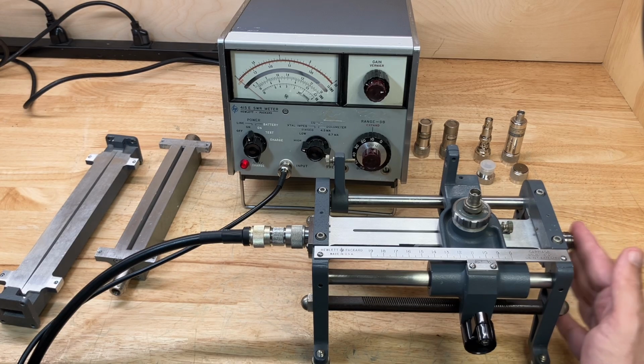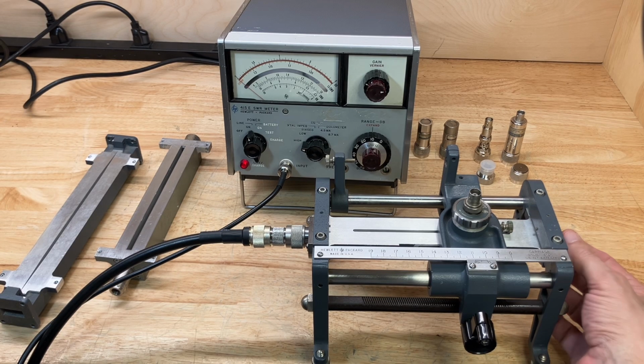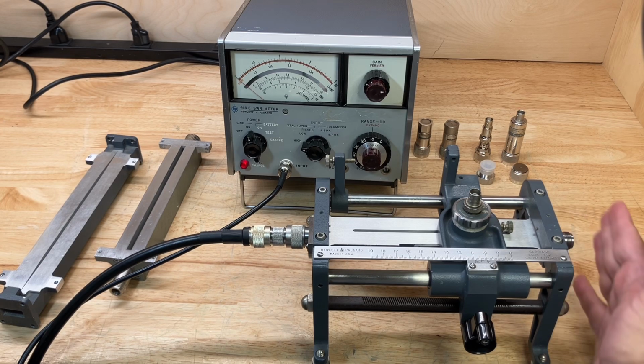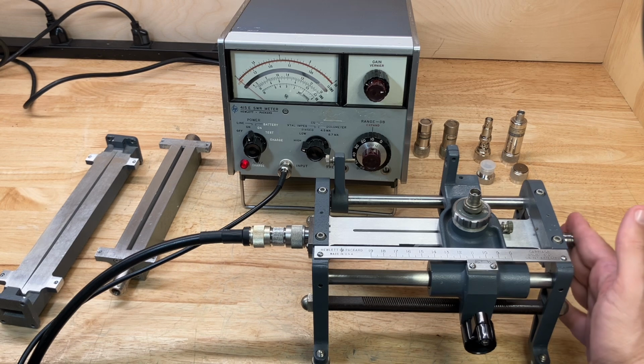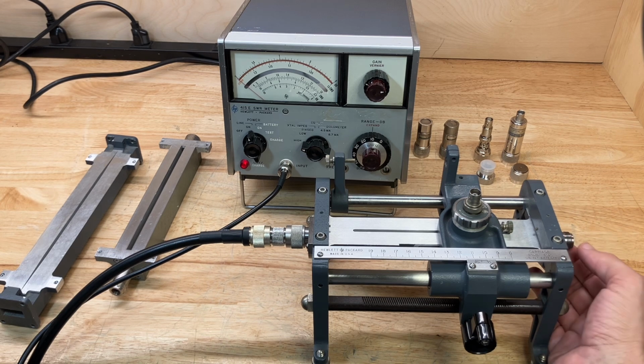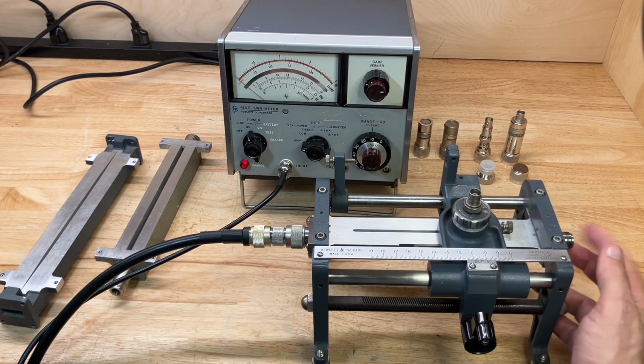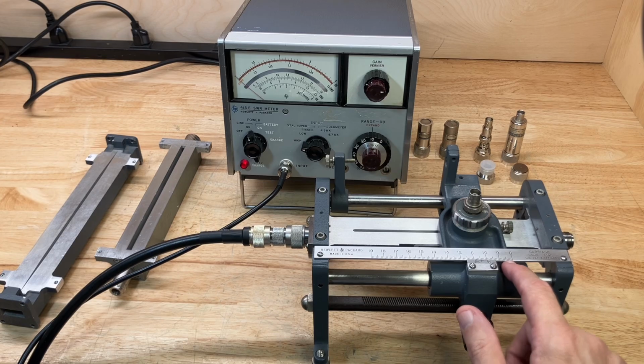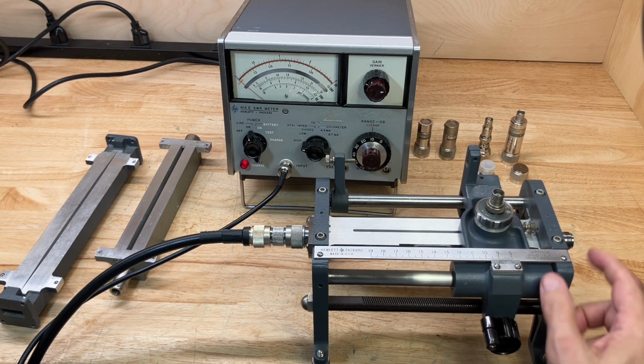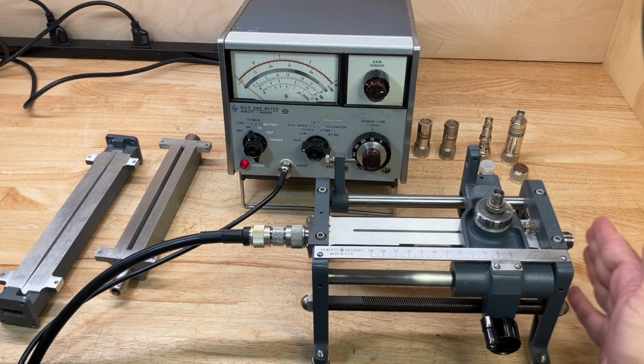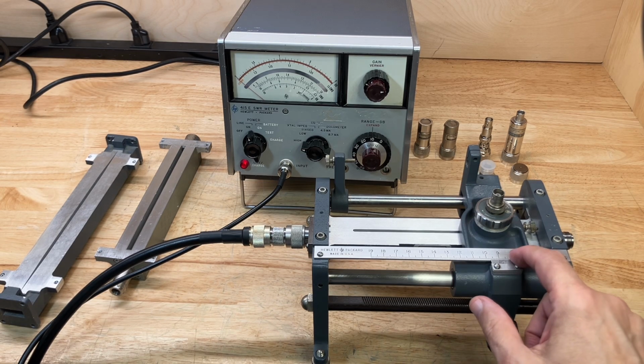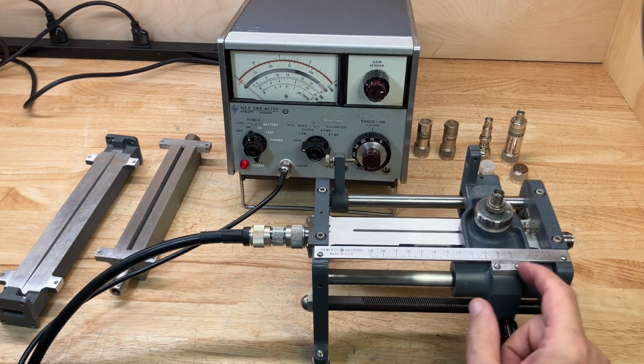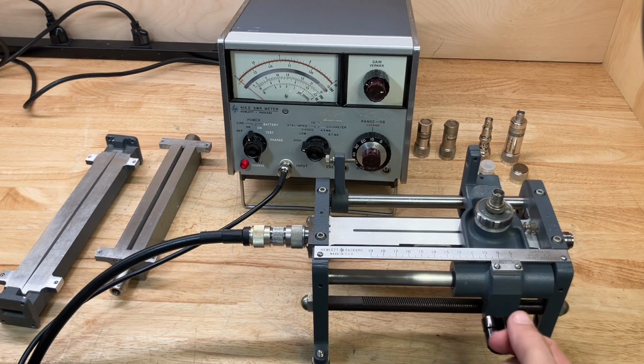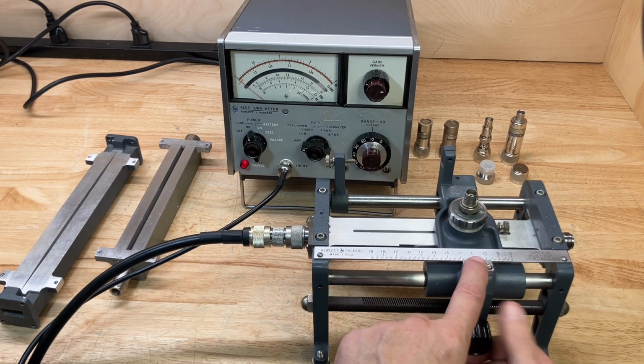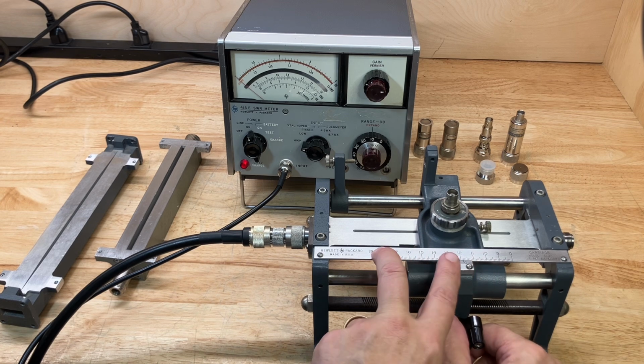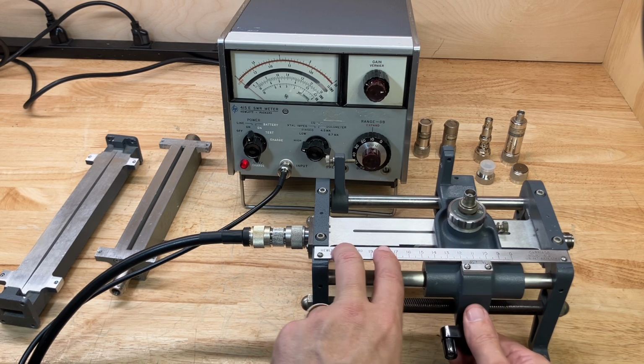And your device under test, whether it's a load or an antenna or an input to another device, goes here at the far end, which would be the reference plane or the test plane. This one happens to have a type N connector at both ends, the input side and the output side. And the scale on the carriage measures the distance from that calibration plane from 8 centimeters. We're 8 centimeters away from here to here, all the way down to 19 centimeters. But really, we're just going to measure the distance between 2 points, either a maximum and a minimum, or between 2 minimums or 2 maximums to make our measurement.